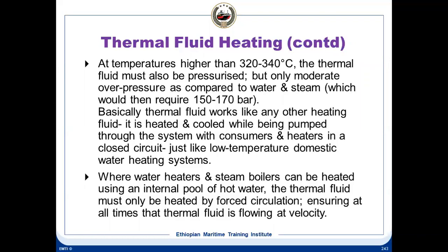Whereas water heaters and steam boilers can be heated using an internal pool of water, just like we have a galley hot water heater, thermal fluid must only be heated by forced circulation. That means the fluid has to be kept flowing through the place where it is being heated, which could either be an oil-fired boiler or being passed over electric heaters. We will come across those diagrams later. So this flow, obviously, will not flow by itself.